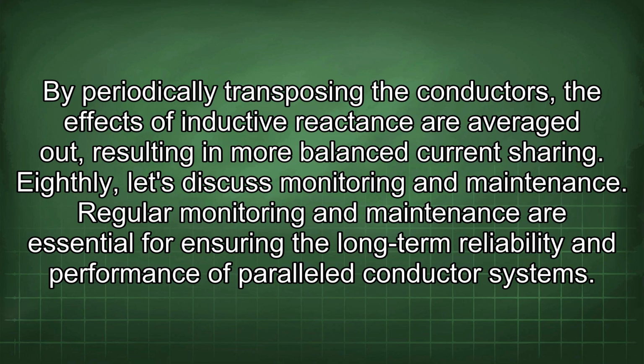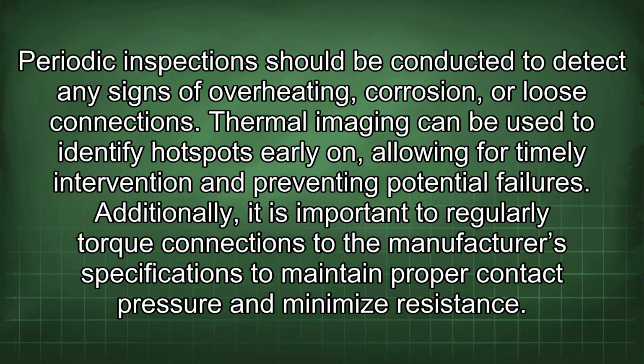Eighthly, let's discuss monitoring and maintenance. Regular monitoring and maintenance are essential for ensuring the long-term reliability and performance of parallel conductor systems. Periodic inspections should be conducted to detect any signs of overheating, corrosion, or loose connections. Thermal imaging can be used to identify hotspots early on, allowing for timely intervention and preventing potential failures. Additionally, it is important to regularly torque connections to the manufacturer's specifications to maintain proper contact pressure and minimize resistance.